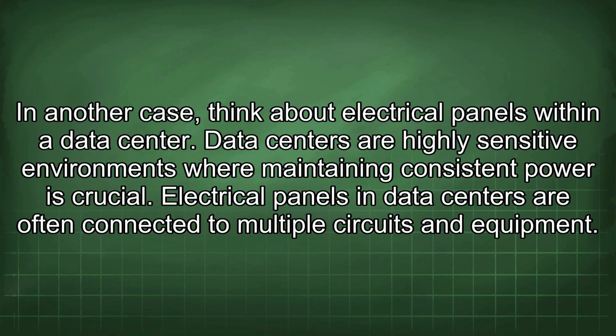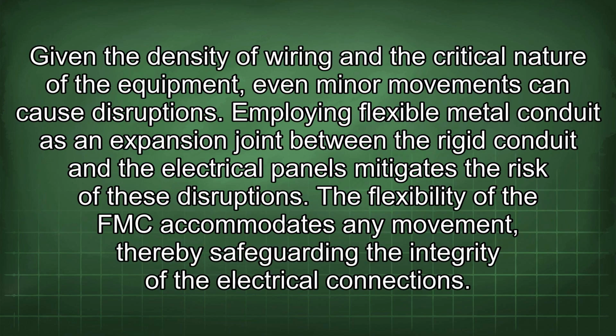In another case, think about electrical panels within a data center. Data centers are highly sensitive environments where maintaining consistent power is crucial. Electrical panels in data centers are often connected to multiple circuits and equipment. Given the density of wiring and the critical nature of the equipment, even minor movements can cause disruption. Employing flexible metal conduit as an expansion joint between the rigid conduit and the electrical panels mitigates the risk of these disruptions. The flexibility of the FMC accommodates any movement, thereby safeguarding the integrity of the electrical connections.